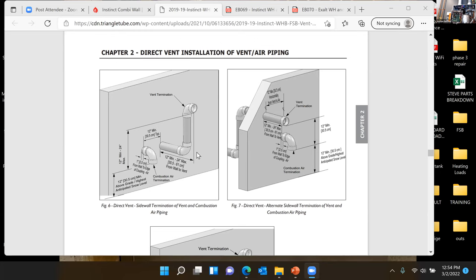So I know that question will probably come up, or some of you are wondering, can I make this shorter? Because by the time you have the overhang in some installations, you could have snow and ice come down and hit this pipe. So we have to be mindful of that. So if we have that minimal, then we have to keep this 12 inch distance. But if we have potentially over that 12 inch, technically it doesn't have to abide by that, and we could have this closer to the wall.